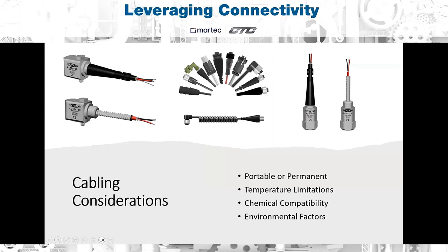I often get asked when an integral cable should be used as opposed to a separate cable connector assembly. You can see the difference in each at the top left. The top shows an integral molded, the bottom shows an integral armored, and then the middle shows separate cable connector options. So I always say that integral cables really should only be used for submersible applications. For all other applications, a separate cable connector assembly should be utilized. And this is because if by chance the sensor or cable gets damaged while installed in the field, it's far easier to replace each component separately as opposed to replacing the entire system when an integral cable is used.